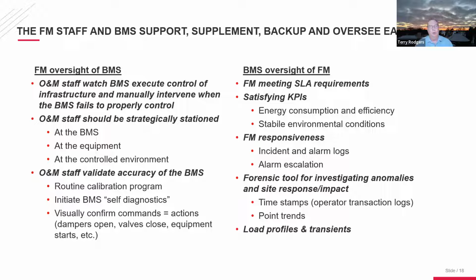When they do command the BMS to do something like swap over a chiller lineup, a good strategy is to put staff at the BMS where they can initiate the actions and monitor on the screens what's occurring. Get staff actually at the chiller plant where they can physically verify that if the command is to open a valve, the valve actually opens, etc., and that the BMS is working correctly.